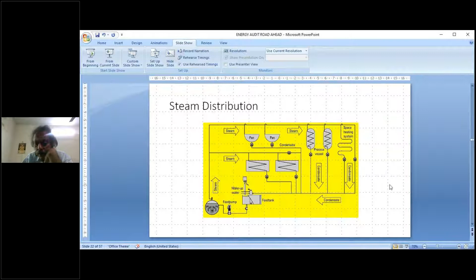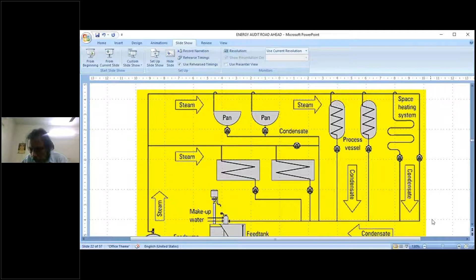Then of course the steam circuit. In a steam circuit, you have steam going into some equipment, and then there is something called a steam trap. You'll be learning more about this in the next few days. The steam trap is a device which will not allow steam but allow only the condensate. So we want the steam to condense and give up the latent heat. The steam trap is a very important device in the steam distribution system. If the steam trap is not working properly, then there will be a lot of losses in the steam system. So the monitoring of steam traps is one of the measures for improving the steam system efficiency.